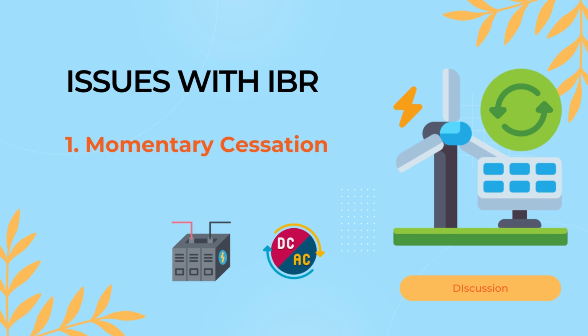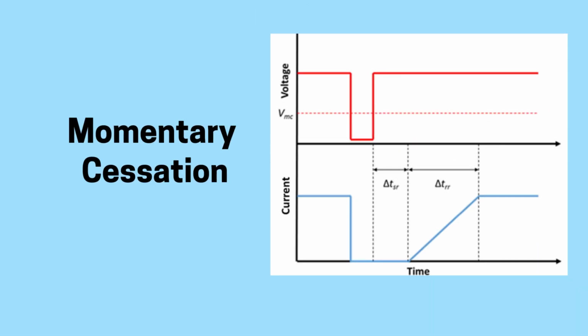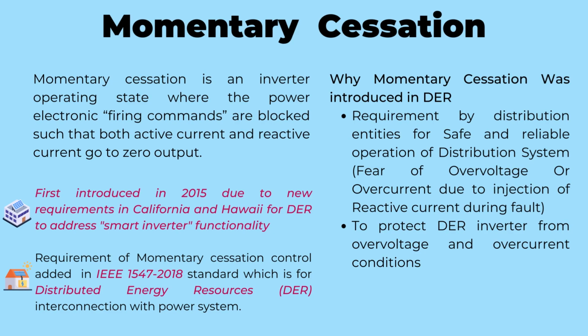Our first stop is the captivating realm of momentary cessation. Momentary cessation refers to a controlling state in which the power electronic firing commands of an inverter are momentarily blocked, causing both active and reactive currents to cease entirely. Picture this: when the voltage detected by the inverter exceeds or drops below a certain threshold, it halts the transmission of any current into the system while still maintaining its connection. But why was momentary cessation control introduced in the first place?